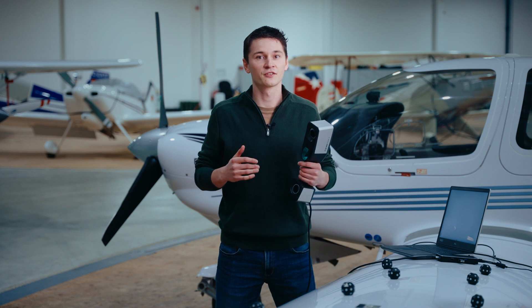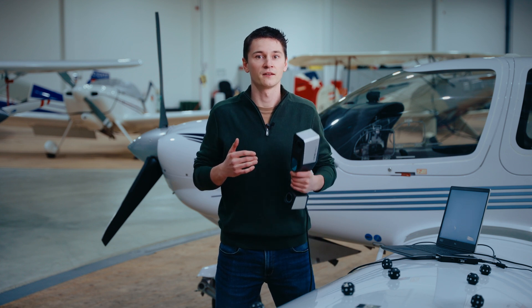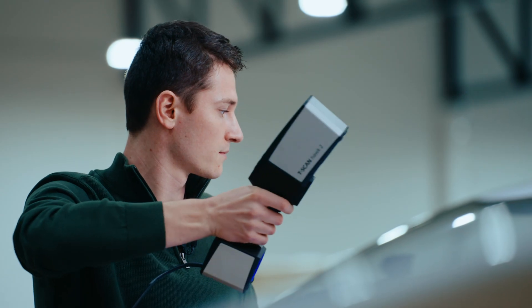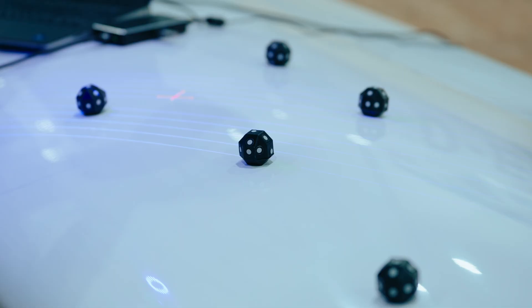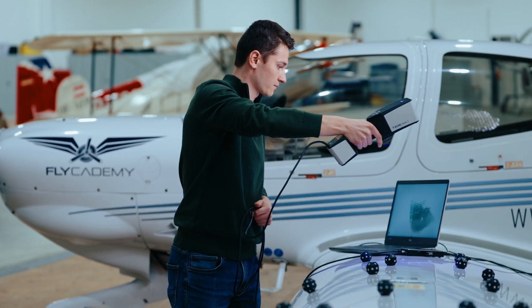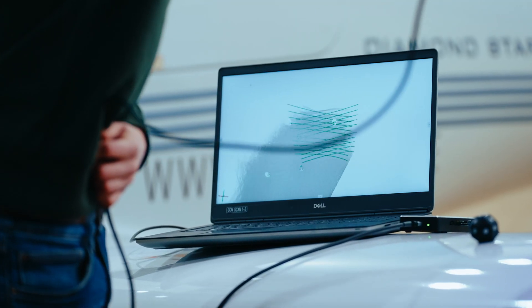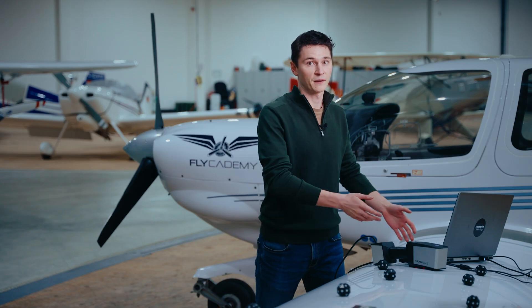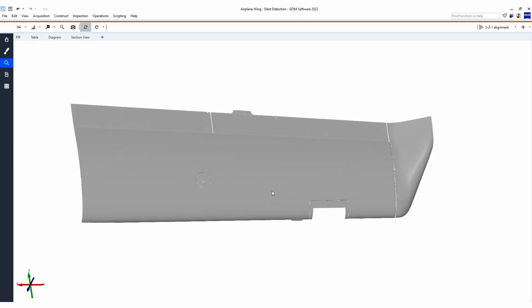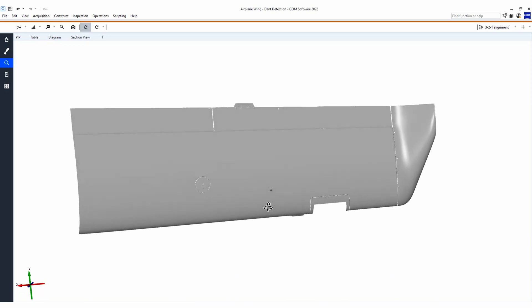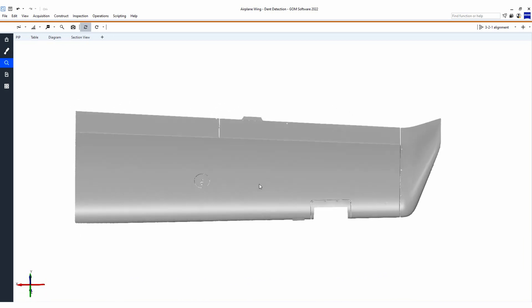Because the T-ScanHawk 2 has a large field of view, the preparation and the scanning happen very quickly. The magic really happens in the inspection software. This software automatically creates the 3D mesh of the measured area and can proceed to different types of inspections.